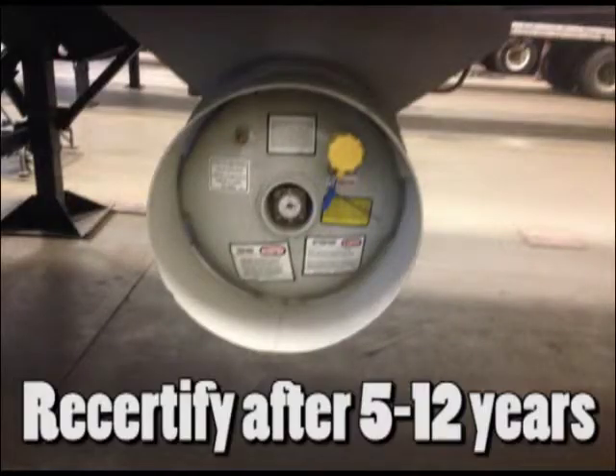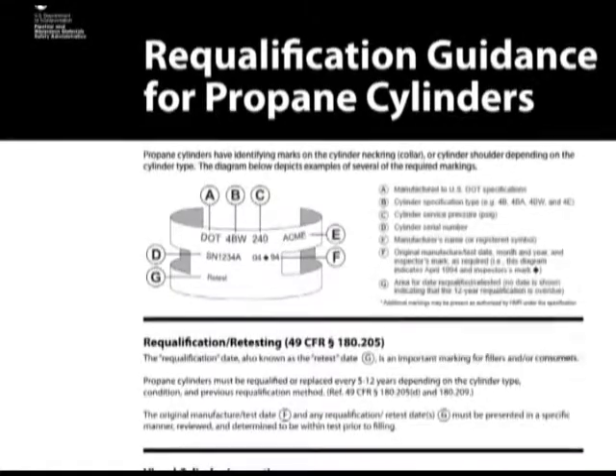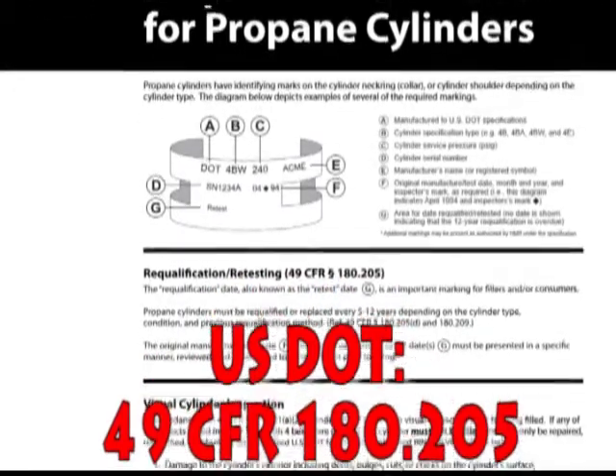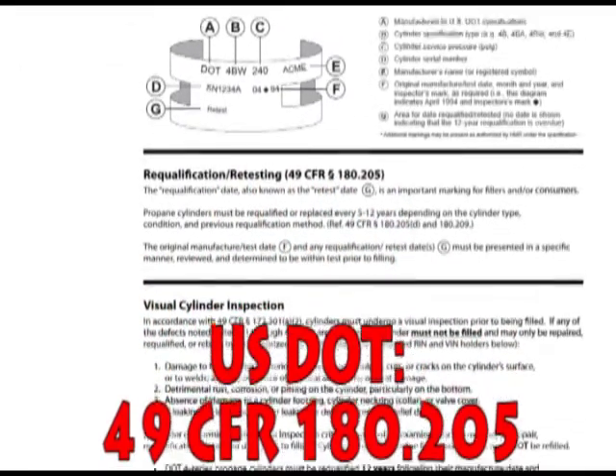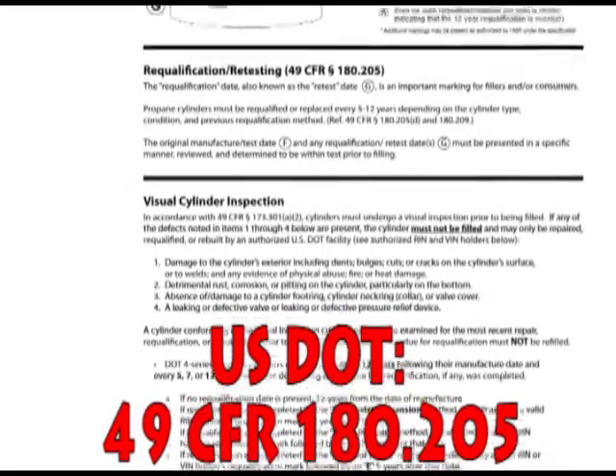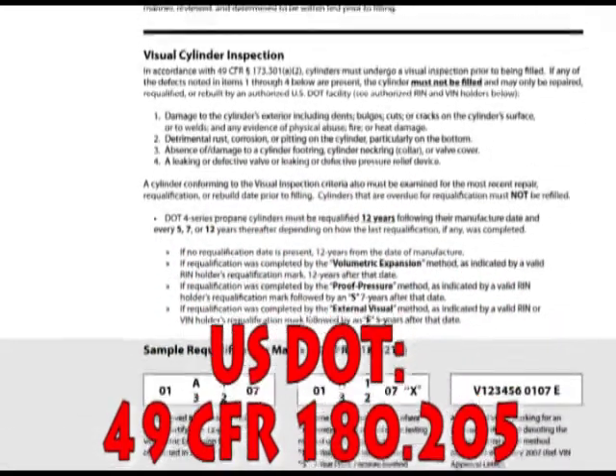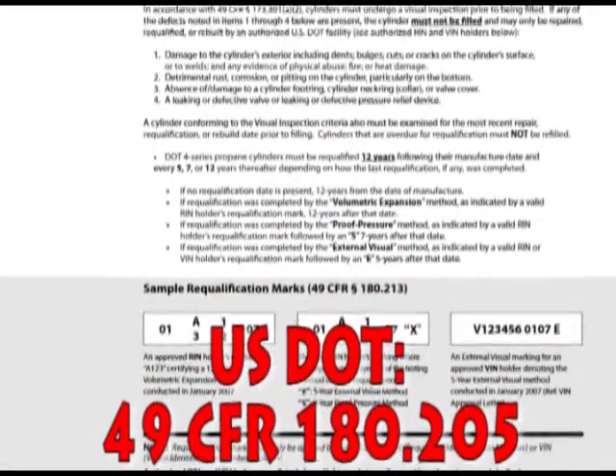All propane tanks need to be recertified for usage after 5 to 12 years worth of operation, depending upon the cylinder type, condition, and previous requalification method. All repairs, requalification, and/or rebuilds must be done by an authorized U.S. DOT facility according to Title 49, Section 180.205 of the Code of Federal Regulations.